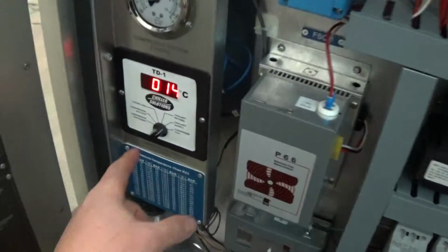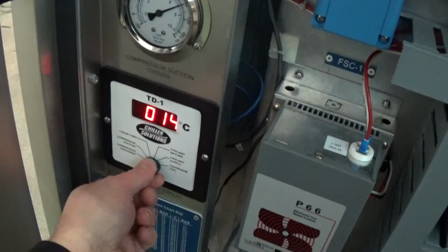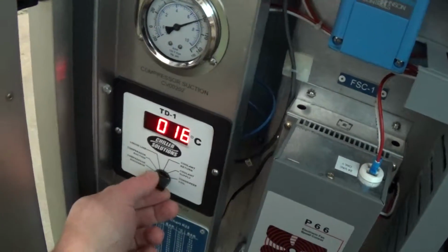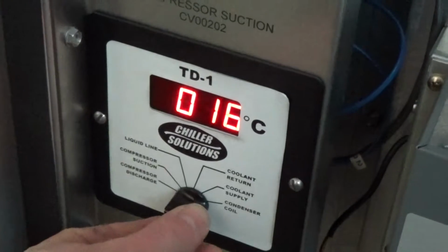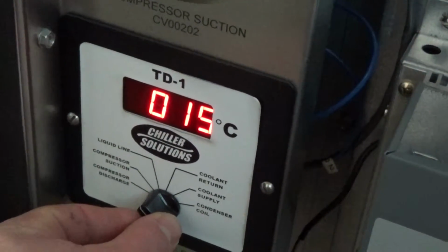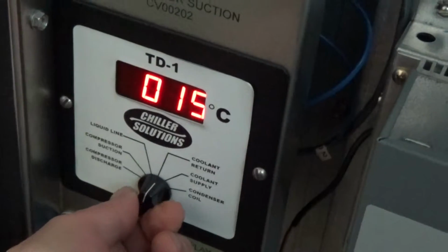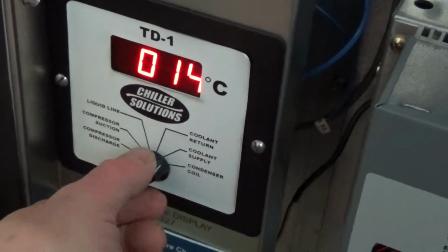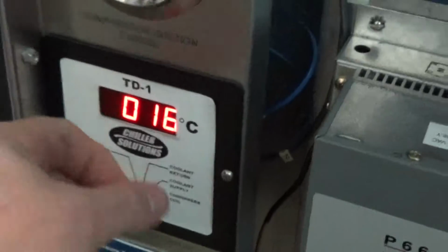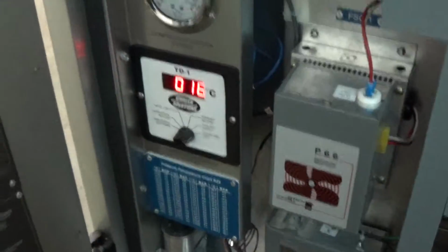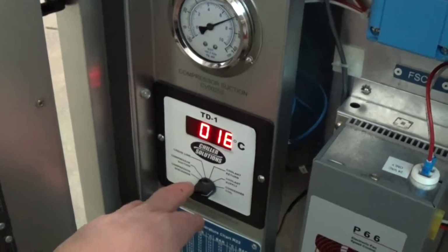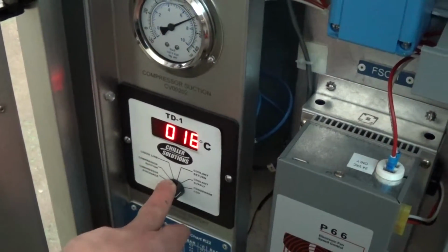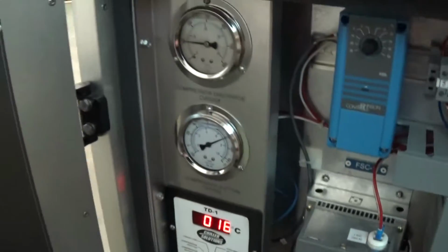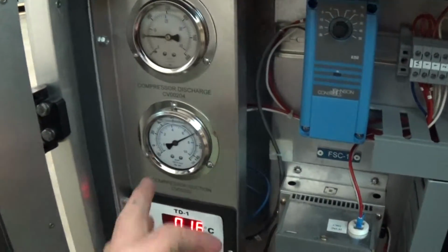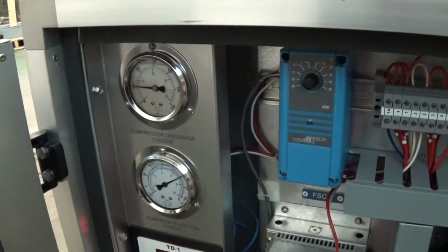What we have here inside the control cabinet is a super nice multiplexing kind of display. It's in centigrade, but it shows things like your compressor discharge temperature, compressor suction temperature, liquid line, coolant return, coolant supply, and condenser coil temperature. Because we're not running or chilling right now, those are all very close. In addition to those 6 temperature parameters, which are outstanding if you ever have to troubleshoot with somebody over the phone, we also have the refrigerant pressure gauges also.